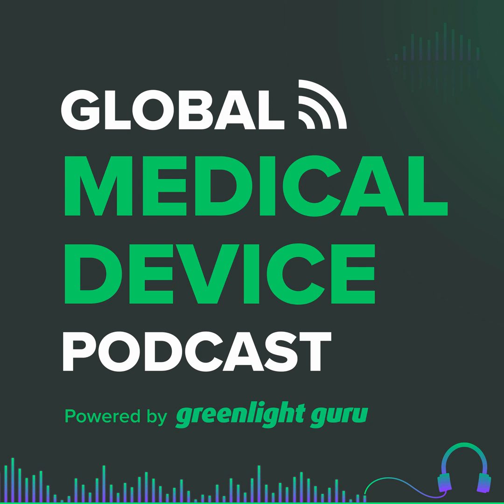So at the end of the day, I'm not sure, to be honest with you, other than maybe a couple of months of FDA review time, that the company's going to really save anything in terms of time and money. And as a matter of fact, I'm not even sure that the company's going to save anything in terms of the review time, because a 510K with a PCCP is probably going to take longer to evaluate than a 510K without a PCCP. Right. So at the end of the day, I'm not sure, again, to use your phrase from before, in all cases, if the juice is going to be worth the squeeze.